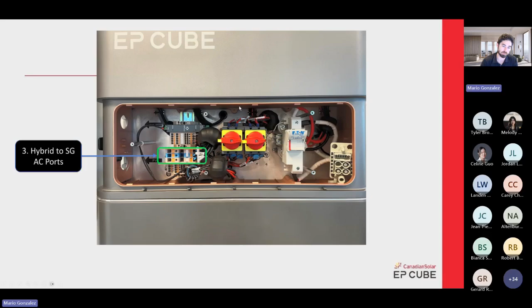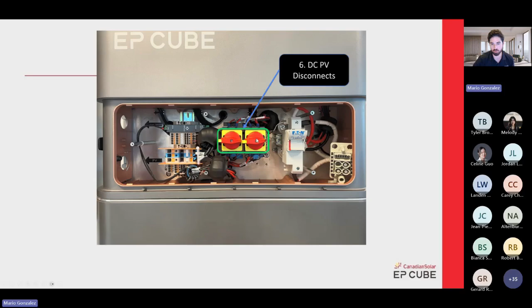In the back, you can see the grounding terminals as well. And the DC disconnects, as I mentioned, 1 and 2 MPPTs, 3 and 4 MPPTs. But then that's the 100 amp battery fuse, and that's the DC battery connector. When you put the inverter on top of the batteries, you're going to have to make sure before commissioning that this guy is plugged in. Again, if not, the DC circuit won't be terminated and you won't be able to do commissioning.